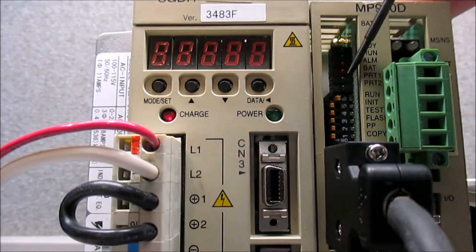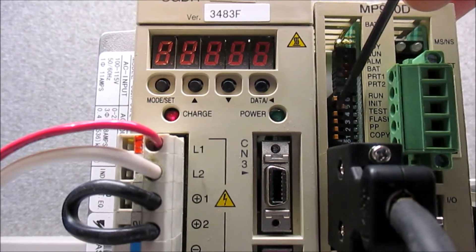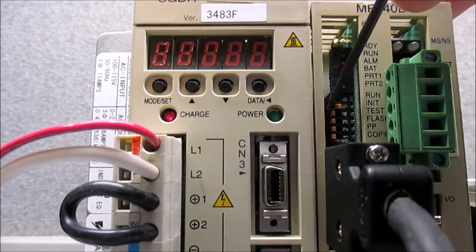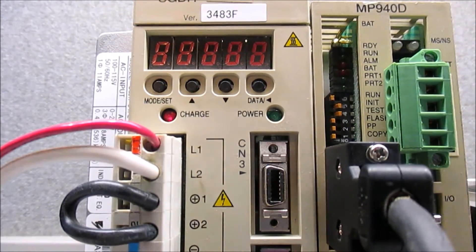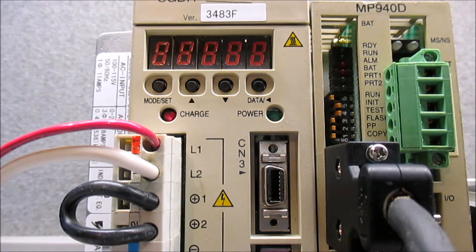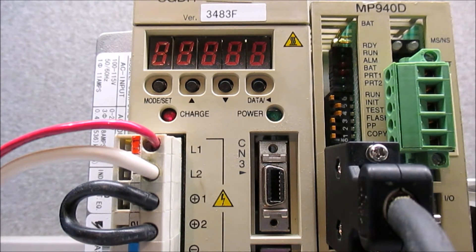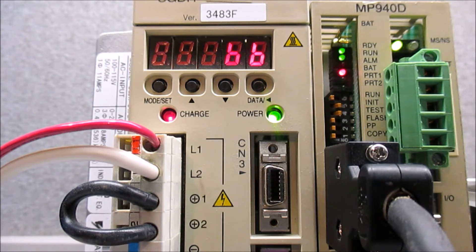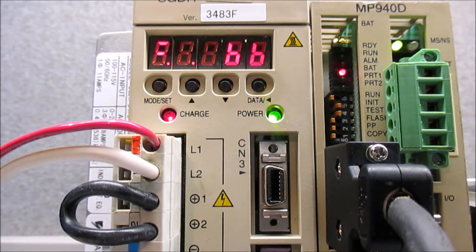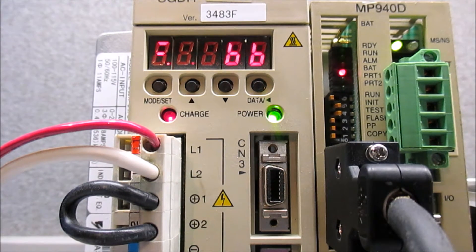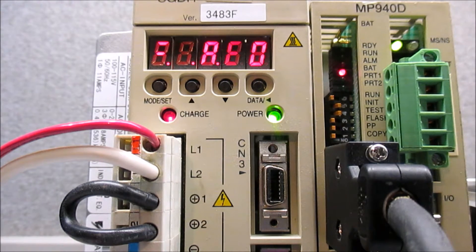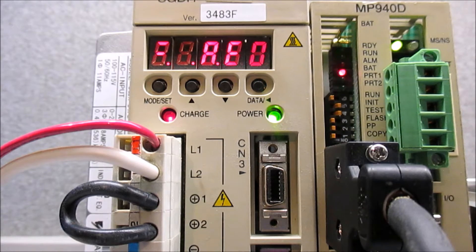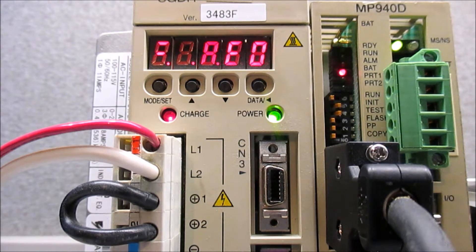And then I'm going to turn off the run switch here and turn on the init and the test, which is switches four and five. And I'm going to power it back up. And if you watch the servo pack, it's flashing BB along with the run and the ready light on the MP940. And now that it's in AEO means that I have successfully taken the memory out.